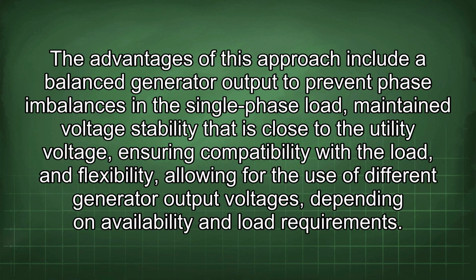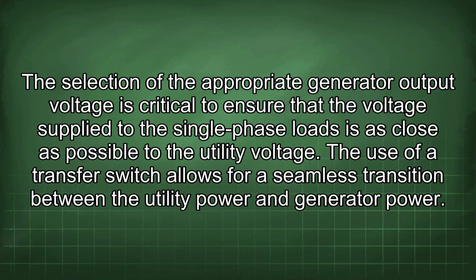The advantages of this approach include a balanced generator output to prevent phase imbalances in the single-phase load, maintain voltage stability that is close to the utility voltage, ensuring compatibility with the load, and flexibility, allowing for the use of different generator output voltages depending on availability and load requirements. The selection of the appropriate generator output voltage is critical to ensure that the voltage supplied to the single-phase loads is as close as possible to the utility voltage.